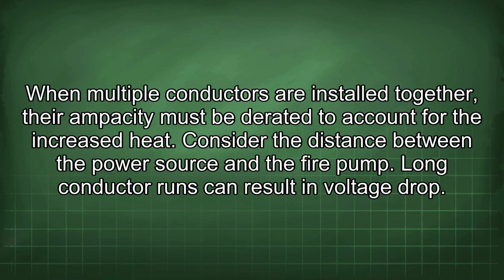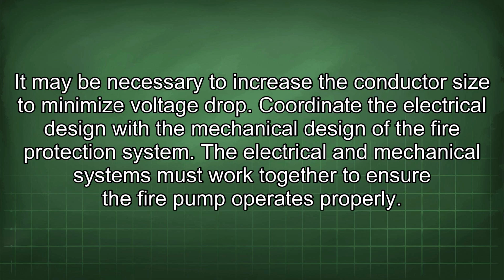Consider the distance between the power source and the fire pump. Long conductor runs can result in voltage drop. It may be necessary to increase the conductor size to minimize voltage drop. Coordinate the electrical design with the mechanical design of the fire protection system. The electrical and mechanical systems must work together to ensure the fire pump operates properly.